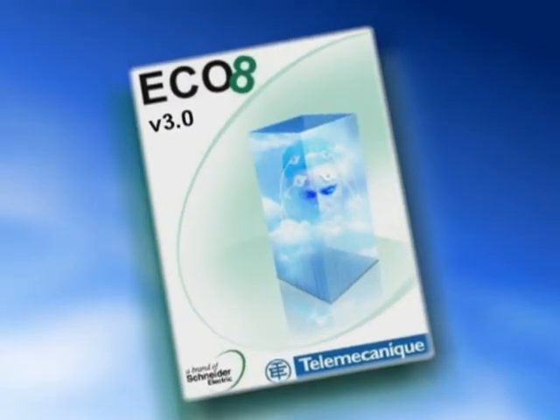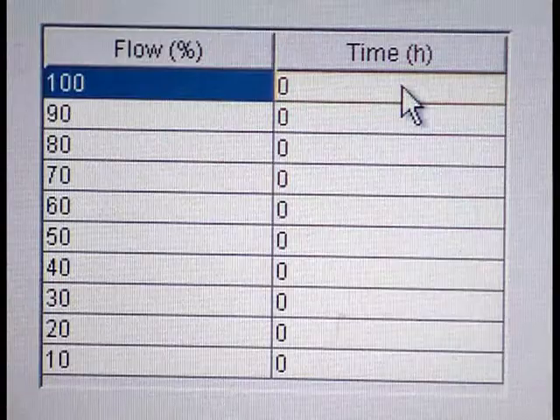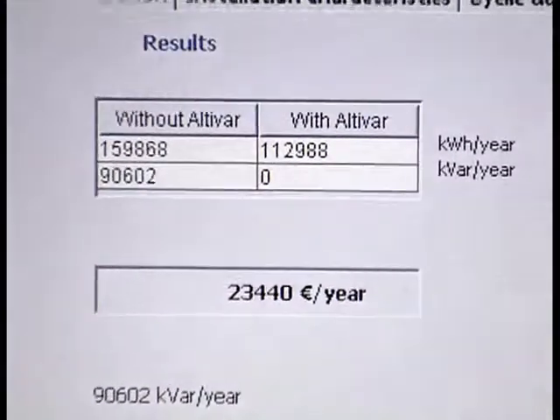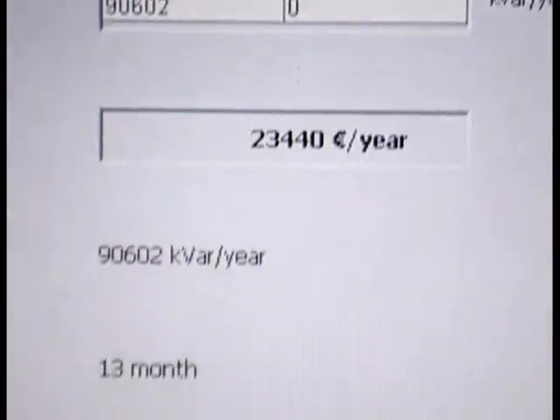The calculation software ECO8 provides a return on investment estimate within the framework of an installation incorporating an Altivar drive. Take for example a 75kW fan: the kilowatt hour price is 0.5 per unit and the cost of the installation is 25,000 units, running at full speed for 3 hours and at half speed for 5 hours, for 300 days each year. The energy saving is 30% and the return on investment is achieved in 13 months.